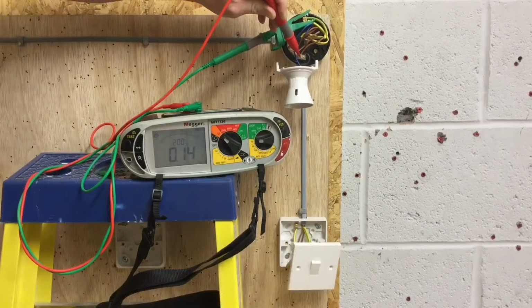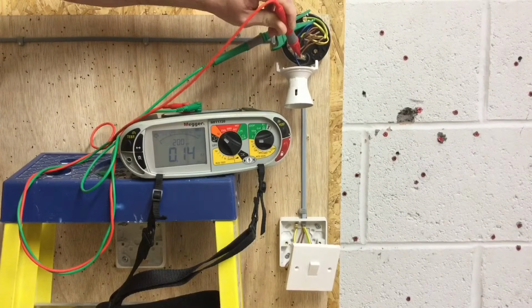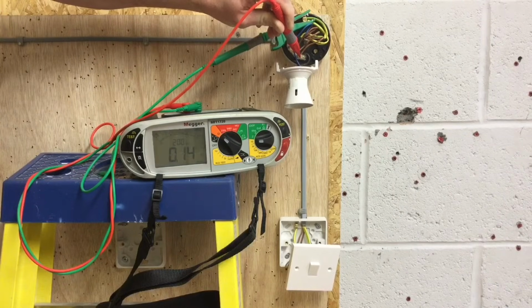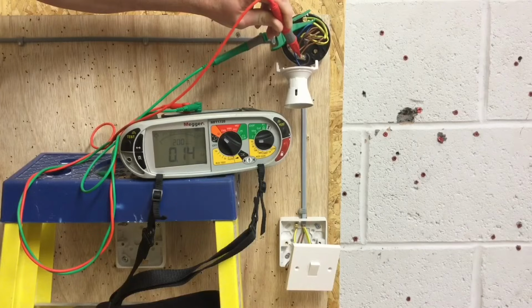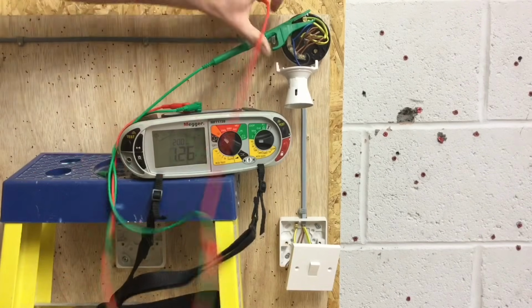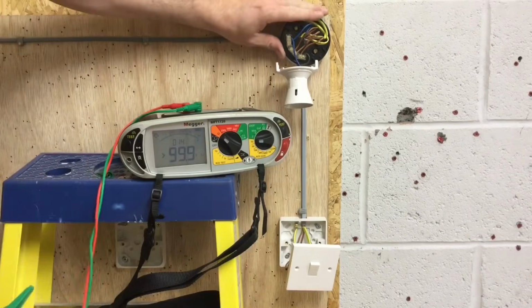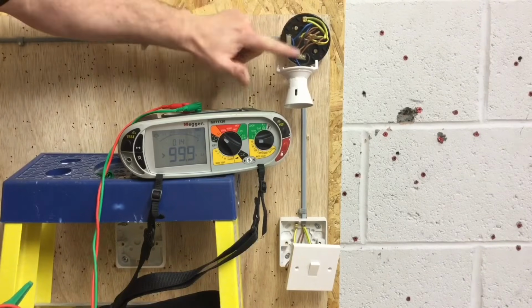Turn it back on, we have a low reading, and it's settled down now at 0.14 of an ohm. By operating the switch we prove polarity. We must leave it in the on position for the insulation resistance test, which is coming later in the sequence. But that isn't it finished. We've only proved the CPC has made its way to, in this case, the batten lamp holder. We've also proved it turns on and off.